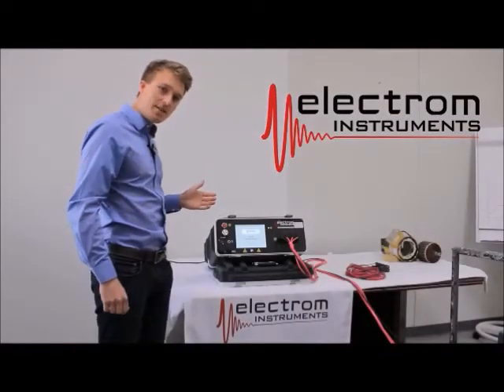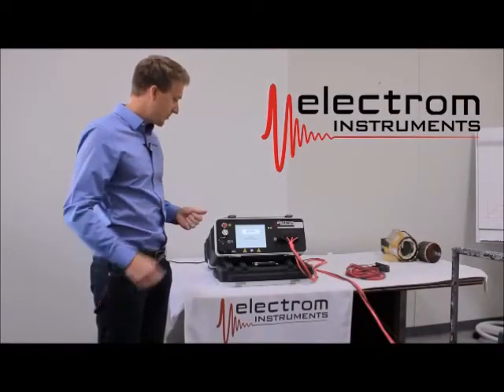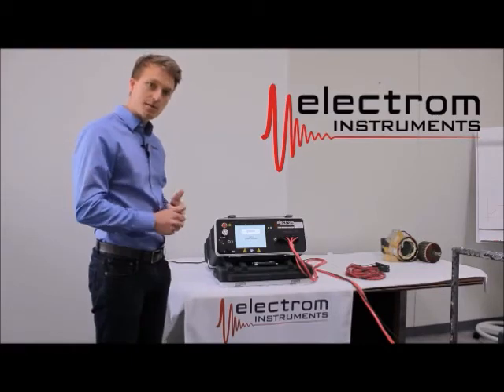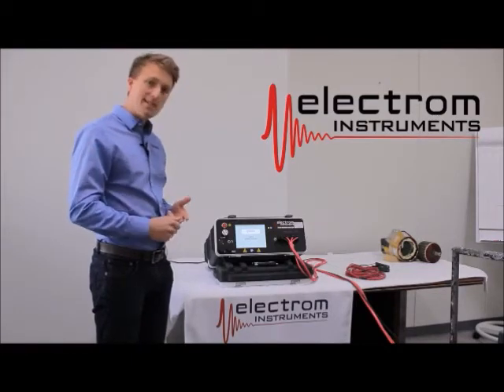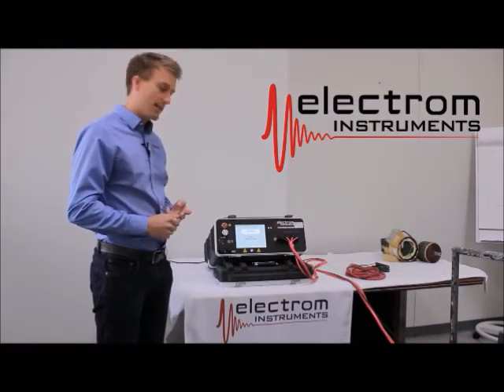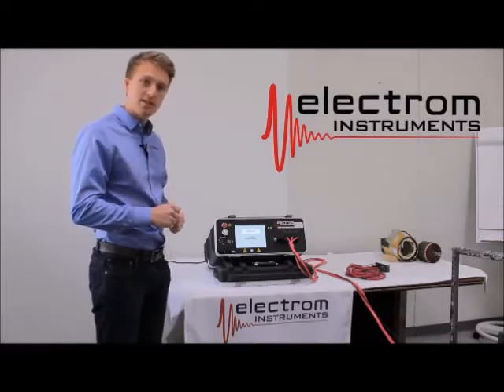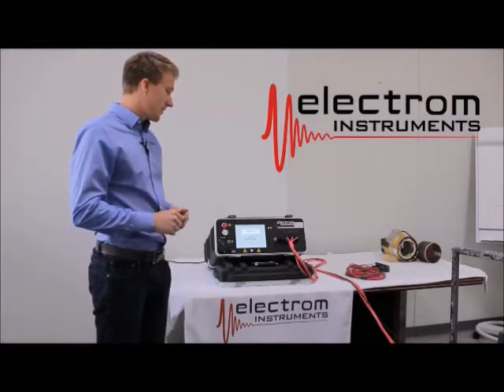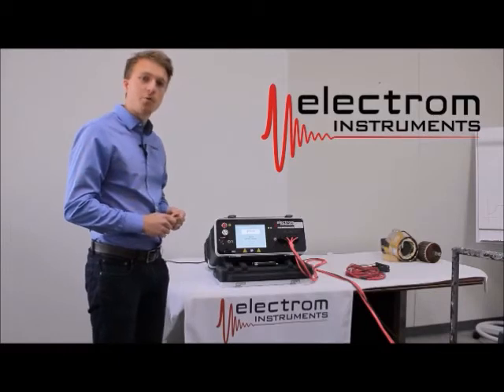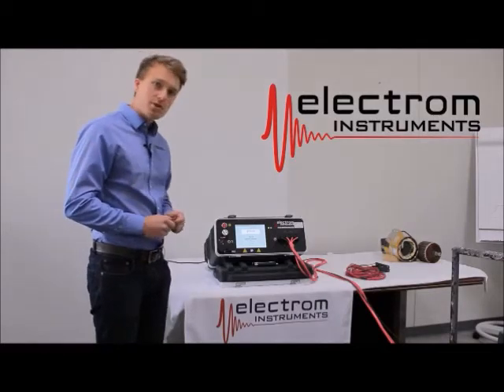This is the iTIG III Model B. It includes milliohm winding resistance, insulation resistance or megohm measurement, DC high pot, and surge test. Optional features include capacitance, inductance, and impedance, advanced multi-coil test feature and reporting software, and partial discharge measurements.